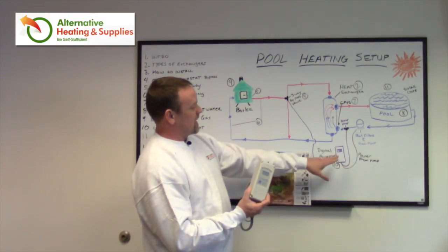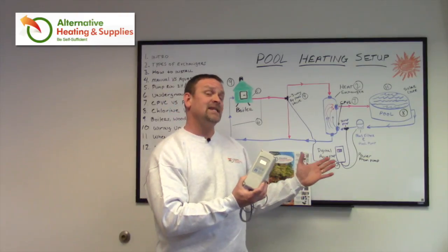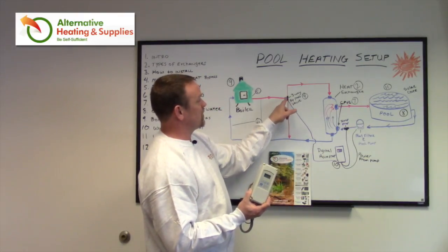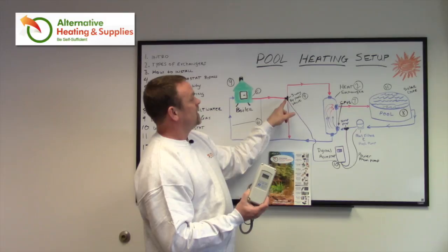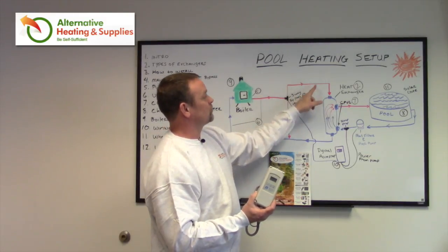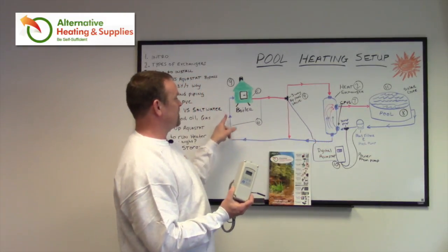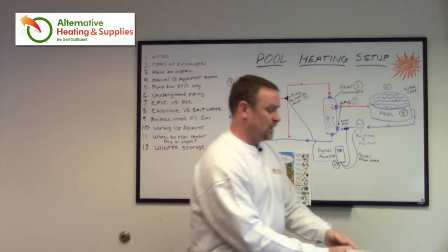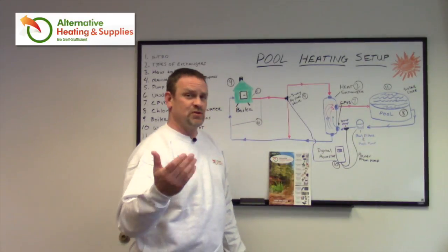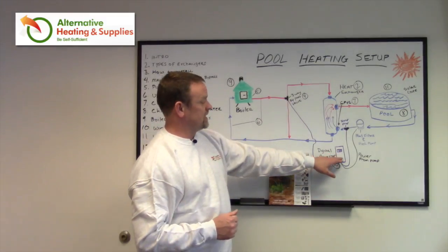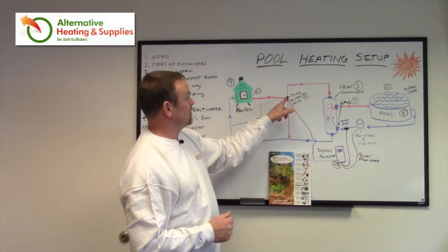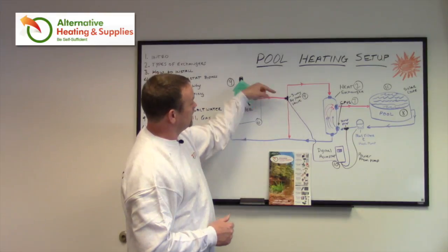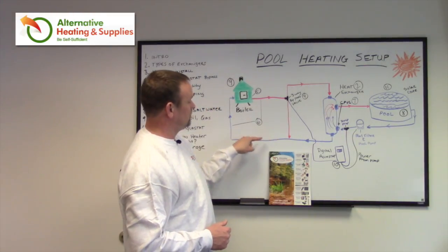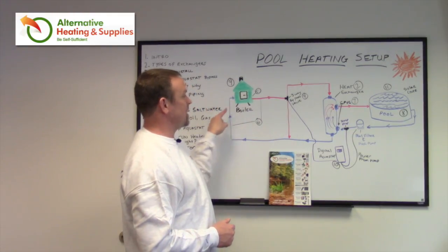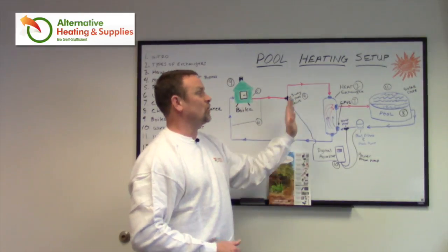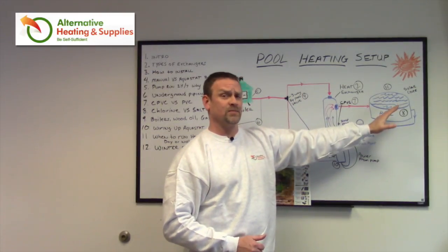Once the aquastat senses it's 80 or 88 degrees, it turns on this three-way valve from the boiler, saying I want the water to go through the heat exchanger and then back to the boiler to get reheated. When the pool temperature has been accomplished and this reads 89, it says we're all set. It tells the valve to shut this way and sends the water from the boiler back to the boiler, just bypassing the heat exchanger. That's how we determine the pool water temperature.